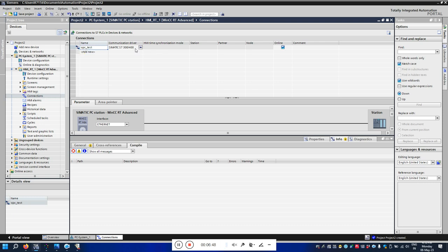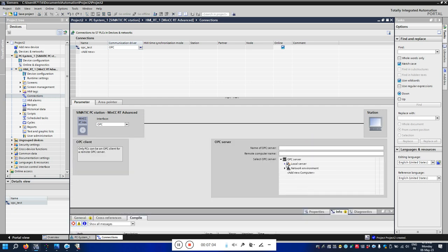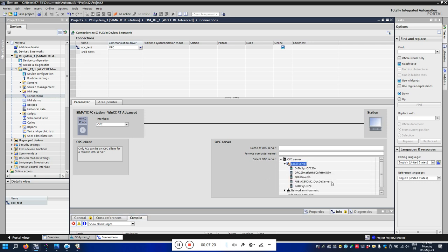First let's make a connection in WinCC to the PLC through OPC. Go to Connections and create a new connection — let's call it OPC Test. Here you need to define how we are going to communicate with the PLC, so select OPC. Go down and you will find the local server. Expand that — it takes a while to load because it's checking all OPC servers installed on your laptop. I'm going to use the ABB AC800M OPC server, which is the one running right now. Just double-click on it and the connection is done.